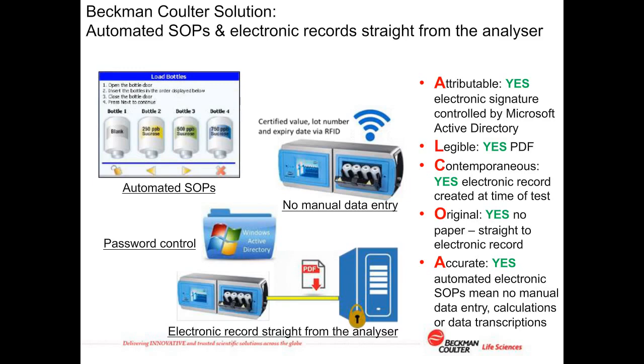Great, thank you. We have a very captivating audience because several questions just came in. This is exciting. Is PDF good to make recalculations and/or trending? So trending, yeah, that's not good. Of course, what most people that I've seen do is that they have a final record for the test itself, but trending is typically done, from what I've seen, either in a LIMS system, a laboratory information management system, or in the case of this type of instrumentation, it's typically done on the SCADA system, the control system for the factory. Or it is possible with this analyzer to export an Excel file or Excel readable file. So you could take the data out in Excel and load it into an Excel spreadsheet. And of course you keep the electronic record, the PDF record, separately as the file to demonstrate batch release, only going back to it if you're called to produce that data.